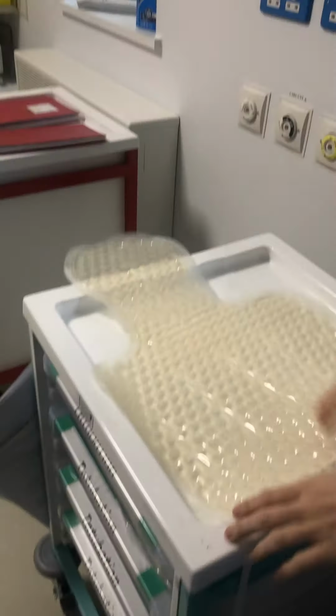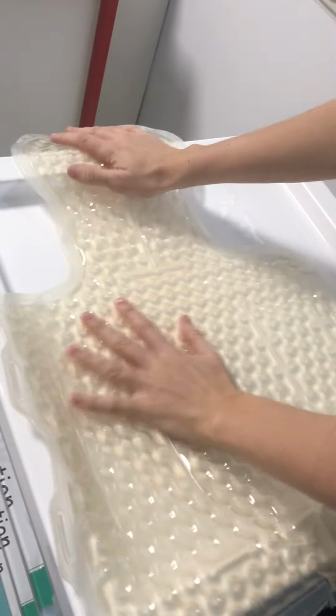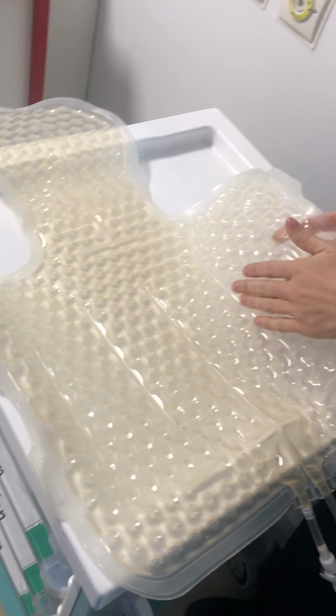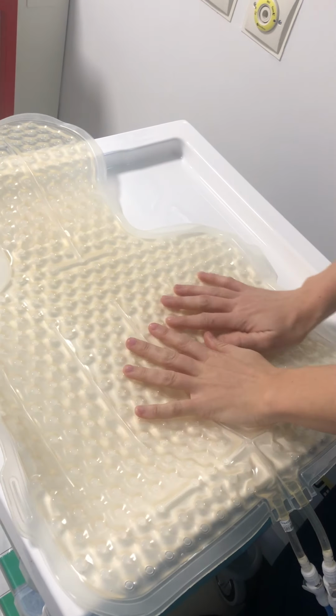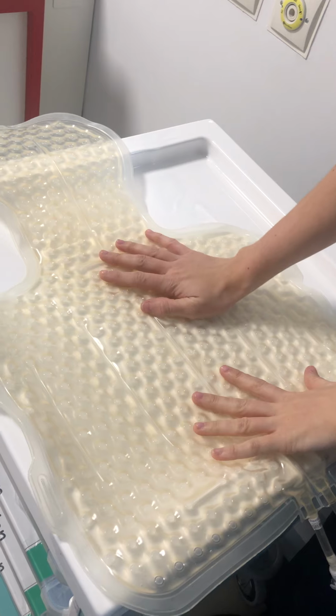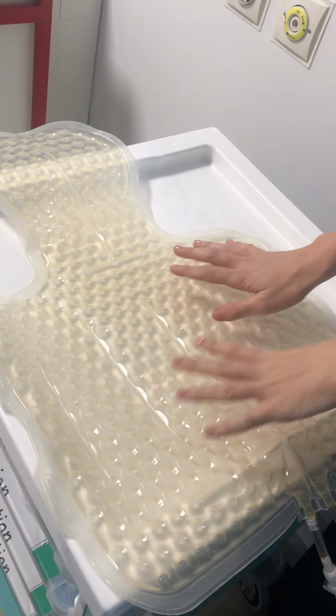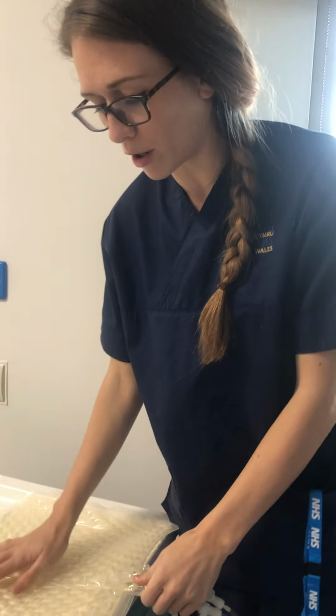There you go. All the bubbles are sucked out. Once you're happy there's no air bubbles, or minimal air bubbles, and the mattress is filling up and getting that honeycomb shape, then you know the mattress is full enough that when you put a baby on there, it's not going to create pockets of air where they pressurise on it, which will cause warm areas, which we don't want when we're cooling a baby.